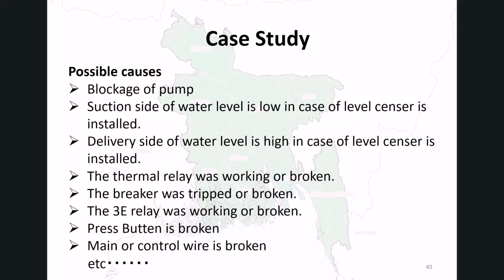In this situation, first you will think about the possible causes. The pump impeller may possibly be clogged. If a water level sensor is installed, the pump will not operate when the suction side water level is low. Likewise, the pump will not operate when the storage tank is full. The thermal relay may have been activated and stopped the operation.